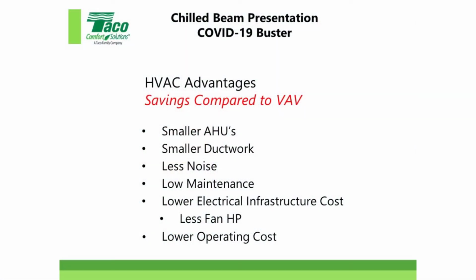Here's some of the savings compared to VAVs. The air handler units can be a lot smaller because you don't have to dry all the air. You only have to dry that air coming into the zones. It's about 30%, 70%. Smaller ductwork, we just showed you that, right? You only need to get that smaller duct coming into the air handlers. Much smaller ductwork. Less noise, right? VAVs, you can hear them come on. Maybe not in this room, but you can hear them come on. In our zones, you don't hear that air coming in. It's very gentle when it comes in. In other industries or other ways to heat and cool buildings, maybe VRF, they talk about how quiet their system is. This system is just as quiet. So maybe for schools or museums or whatnot.